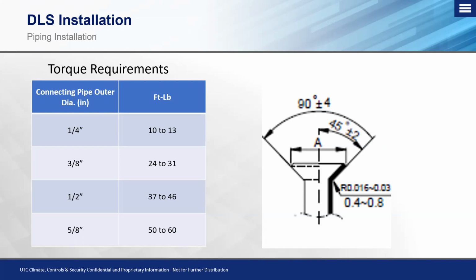And then secondly, we need to make sure that we are torquing down our flare nuts. Good and tight does not cut it. We need to make sure, one, what is our diameter of pipe? And two, what foot-pound of torque we need to torque down on that flare nut. So for this example, you'll see 1/4 inch requires 10 to 13 foot-pounds of torque. 3/8 pipe requires 24 to 31 foot-pounds of torque. 1/2 inch requires 37 to 46 foot-pounds of torque. And finally, 5/8 requires 50 to 60 foot-pounds of torque.